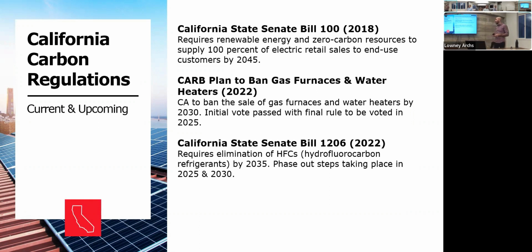And then there's also another bill at the bottom that's about refrigerants, because refrigerant leakage is also a big contributor to ozone depletion and climate change effects. So we are also phasing out the refrigerants step by step, and most of today's widely used refrigerants will be banned by 2035 and will be replaced by more natural refrigerants like CO2.